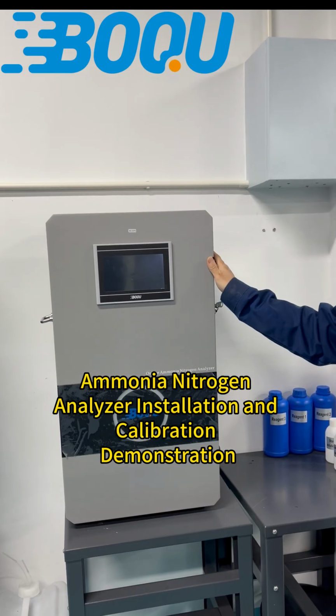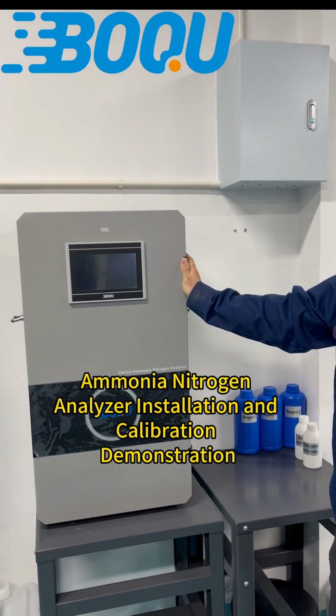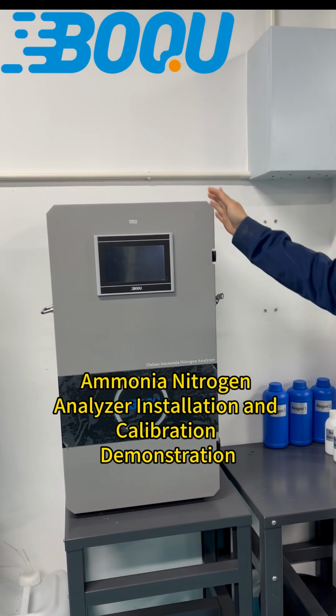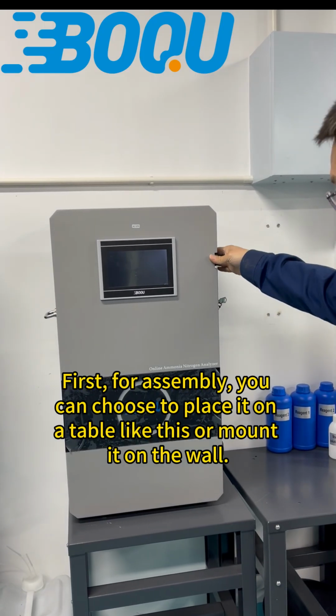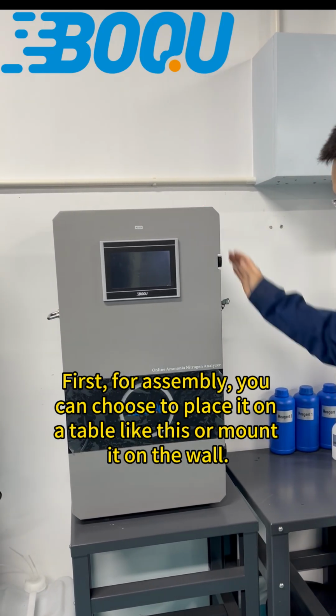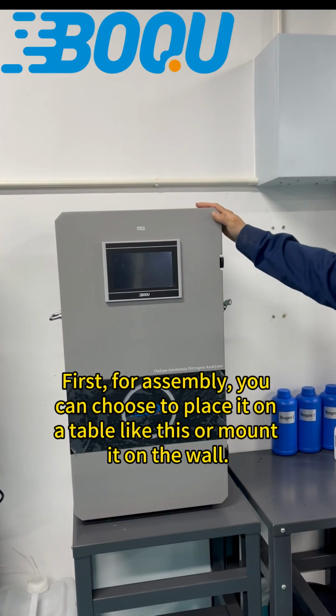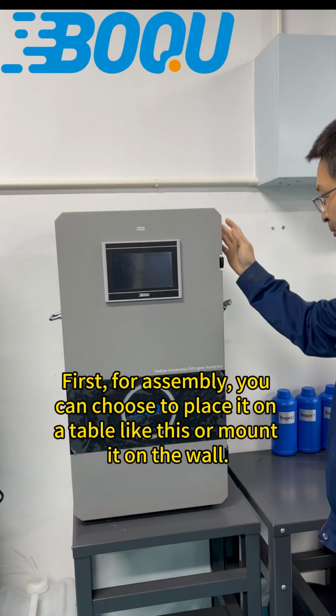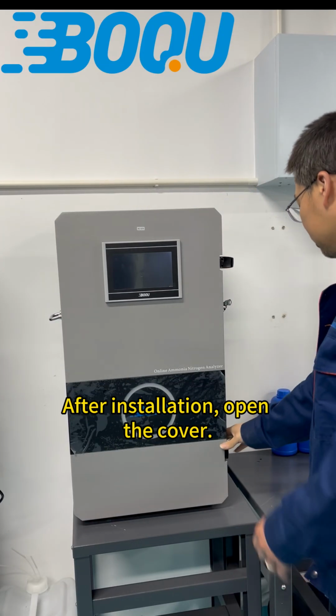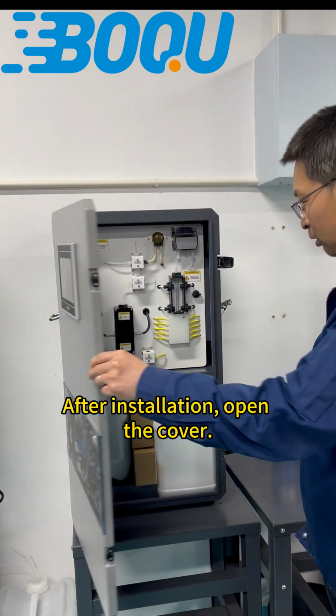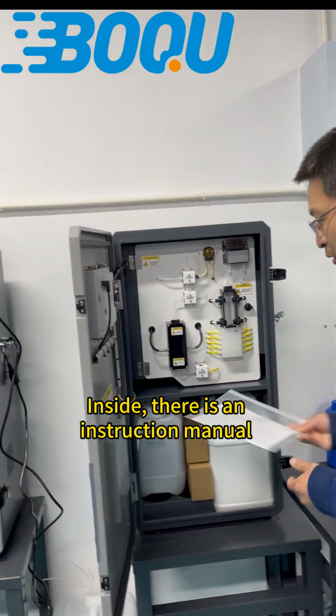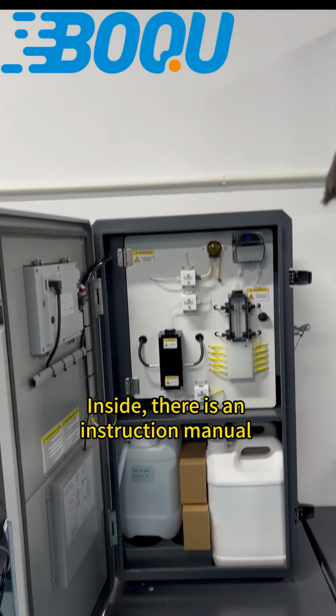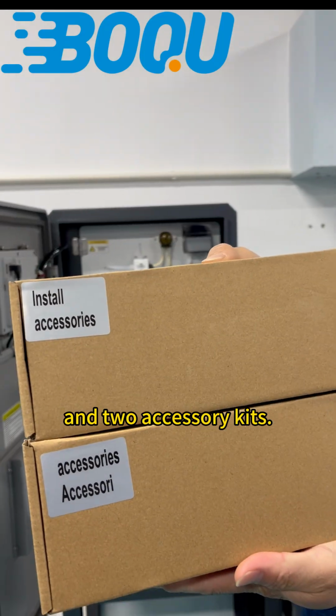Ammonia nitrogen analyzer installation and calibration demonstration. First, for assembly, you can choose to place it on a table like this, or mount it on the wall. After installation, open the cover. Inside, there is an instruction manual and 2 accessory kits.